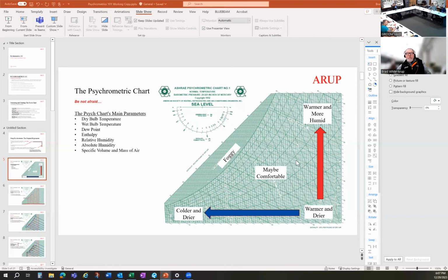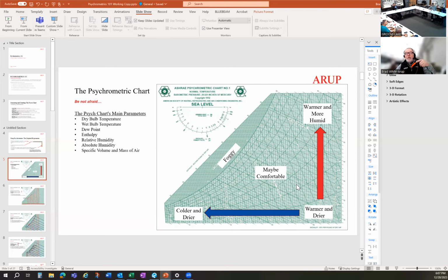And every point in this chart has a certain property. And one of the things I ask my students to do is I call it the dartboard test. As part of your quizzing, you take a push pin and you push it anywhere in that chart. Just drop a pin here, here, or here, anywhere, just blindly, and tell me everything about that point. You can tell me the density of the air at that point. You can tell me what the total heat content is. You can tell me the temperature, the relative humidity, the absolute humidity, as well as, as I mentioned, the weight, and where its dew point is. What temperature is it going to? Is that moisture in that air going to condense? So again, any factor you want to know, it's on this chart. It's embedded in this, and that's why these things are very useful.